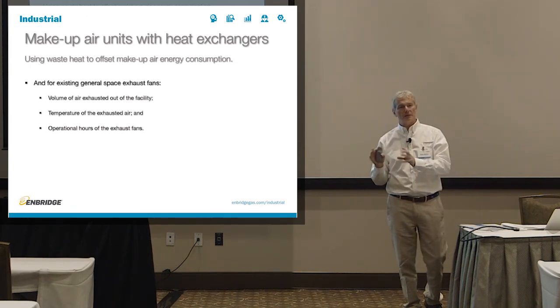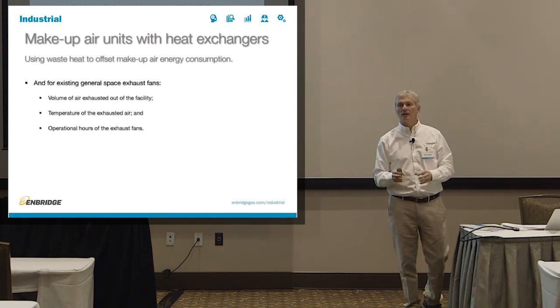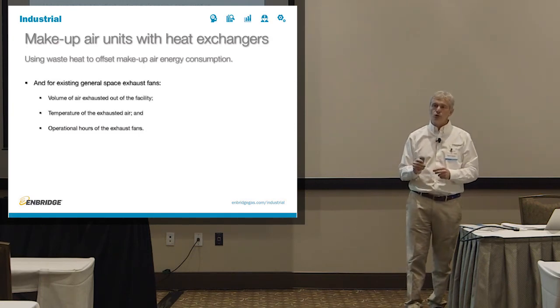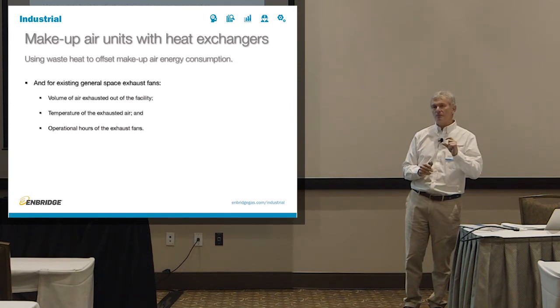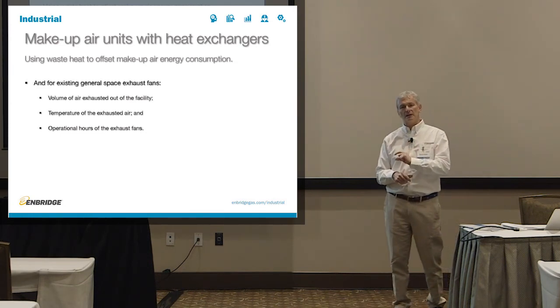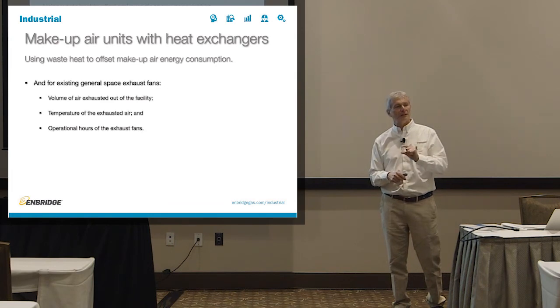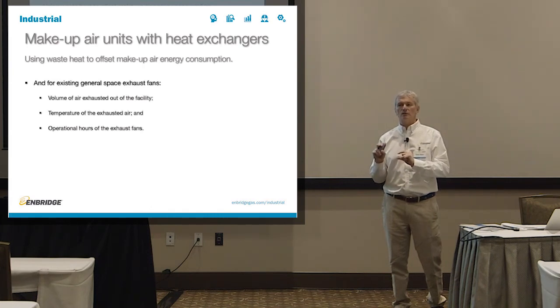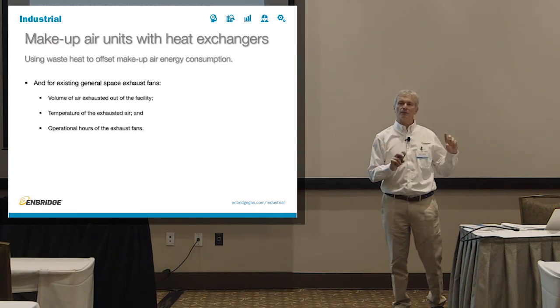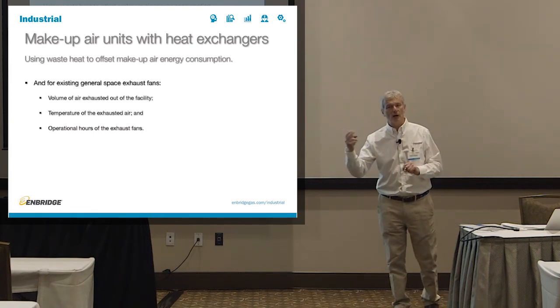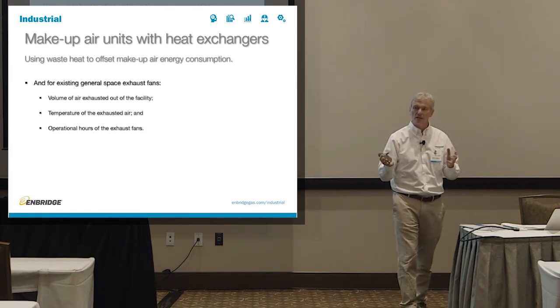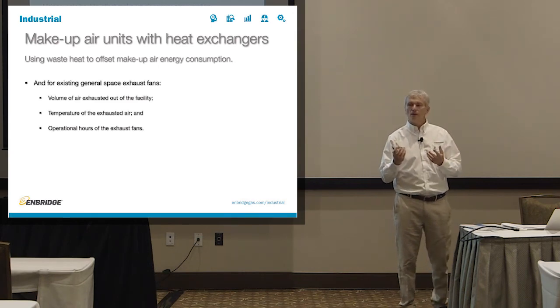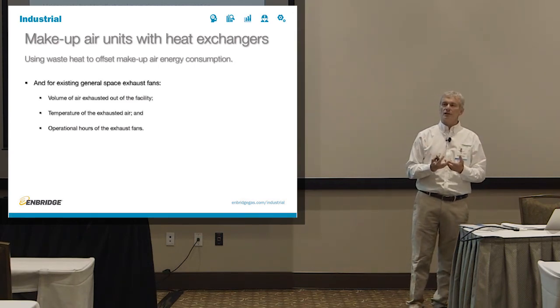Usually what we've seen is 5 to 6 times the amount of exhaust air than what people need. Usually you have, if not enough, then even more than enough makeup air coming in as it is. So if you look at your makeup air and you have 10,000 CFM of makeup air coming into the facility and you have 100,000 CFM of exhaust, the first question should be, why do I exhaust 100,000 CFM? Not, I have 90,000 CFM of makeup air to make up for. And remember how we talked about how hot areas of the plant like to be exhausted in the summertime because it's hot? Usually that's where the additional exhaust comes from.